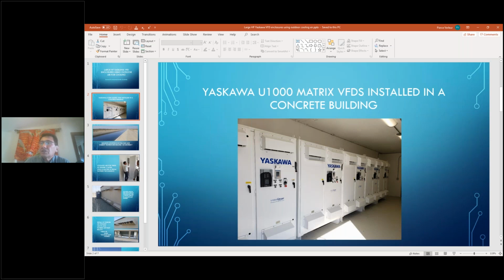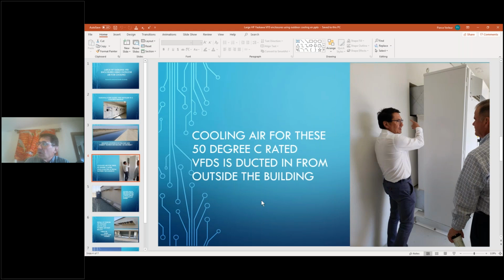By punching a couple of holes in the building wall, and this is prefab, so we had to plan this out, we were able to draw outside air in, outside air. Why? Because this is an outdoor duty rated enclosure. We got these all over the Central Valley standing on concrete pads out in the full sun.